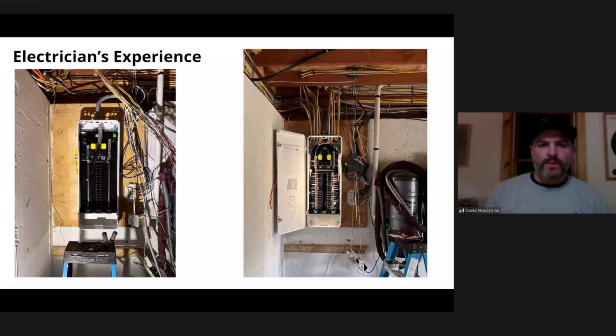Also, one thing I'd like to mention is that it's 32 circuits that are controllable. So if you have 42 or 44 circuits, you can tandem those down into one single breaker, but you will only see and measure those circuits combined, not each one separately. So what I like to do is put all the lighting at the bottom and group it up, since you're not really going to need to measure all your different lighting loads separately.